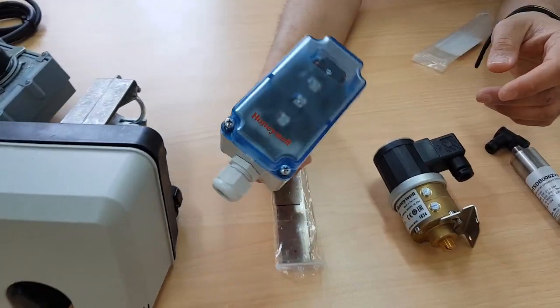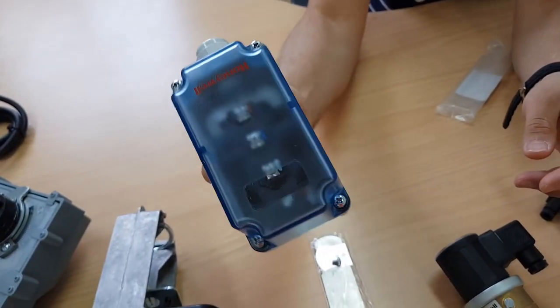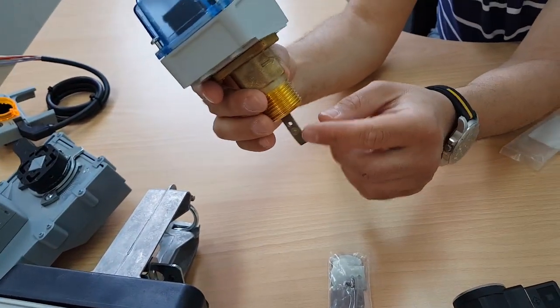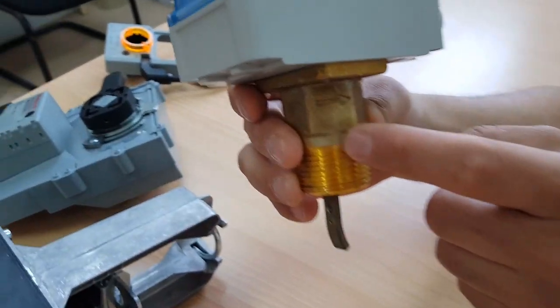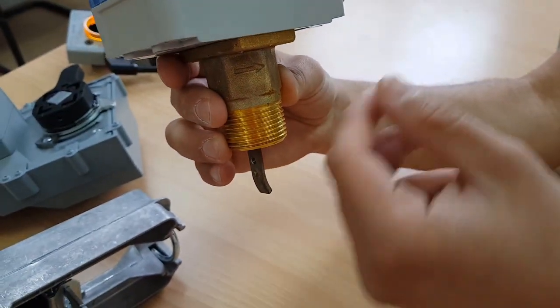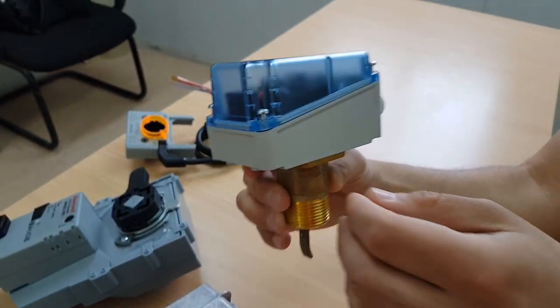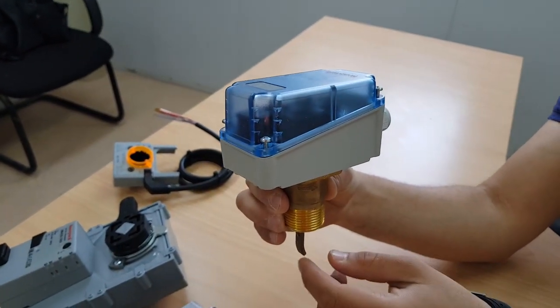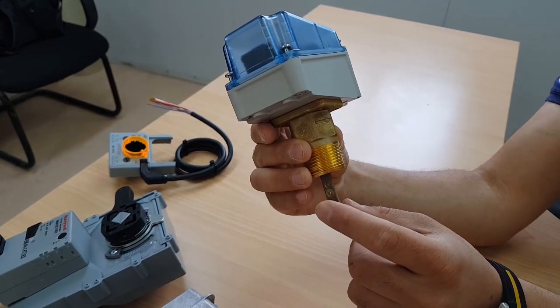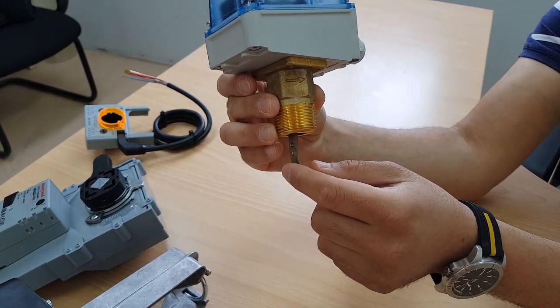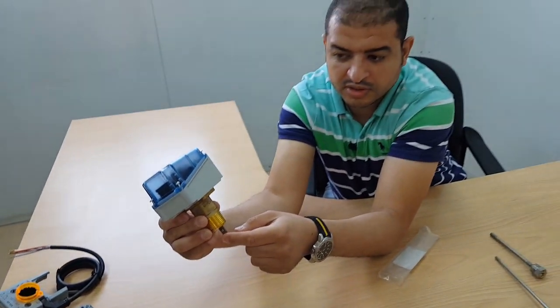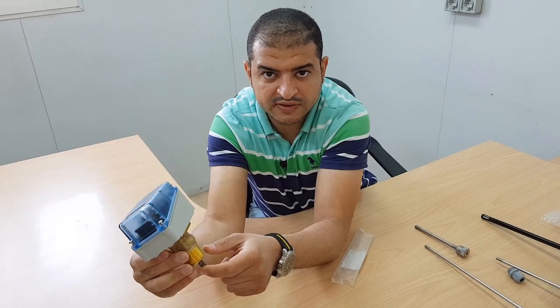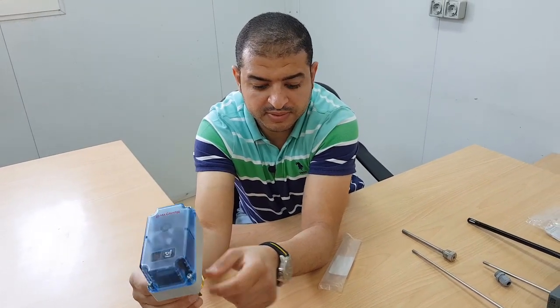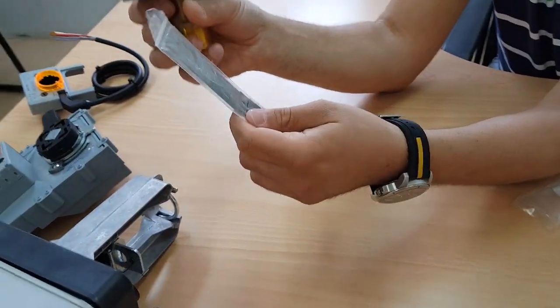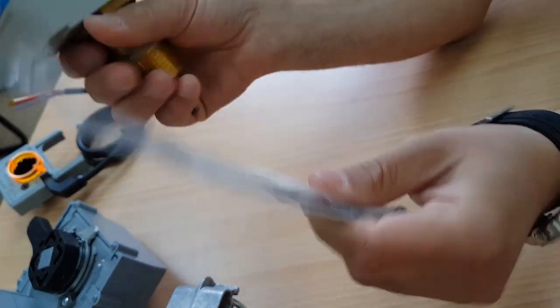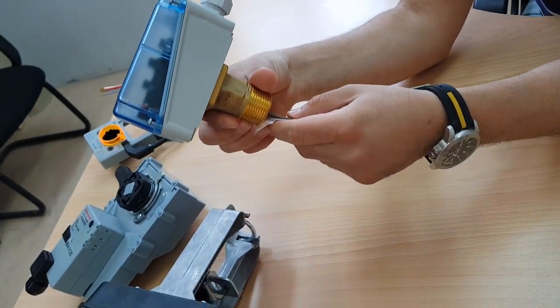Here, this is a flow switch, to check the status of the flow. This is the arrow for the flow. So out from the pump, if the flow is going this way, this is the correct installation. In this status, it is normally open. So if there is a flow, it will be converted to closed, giving a status that there is already flow in the pipe. This is the paddle. We have different sizes of paddles, which will be connected here to the flow switch.